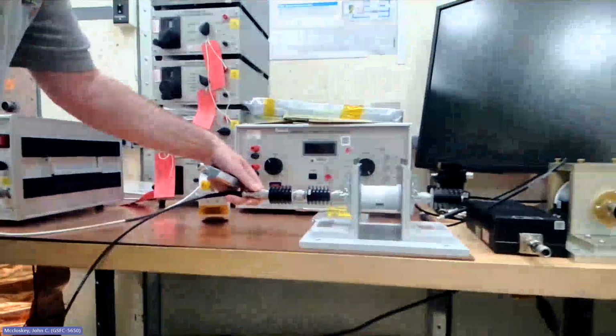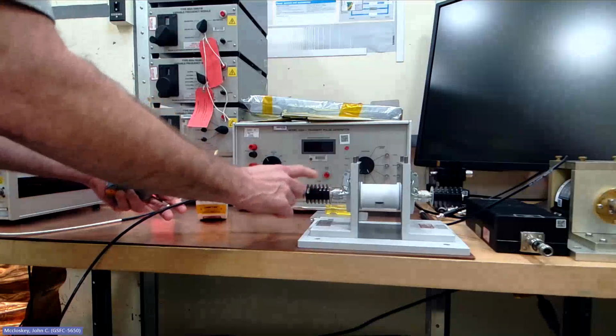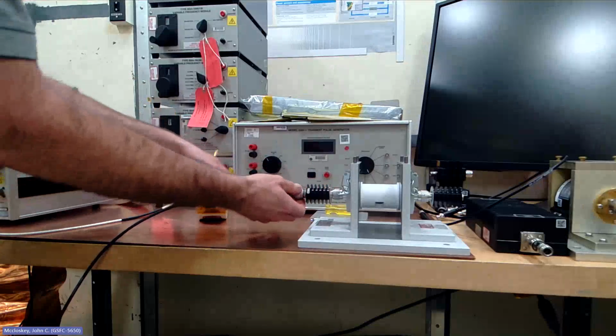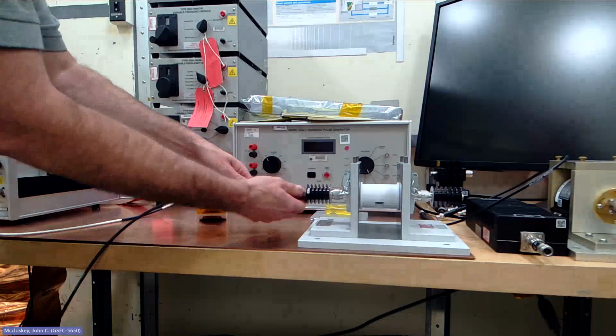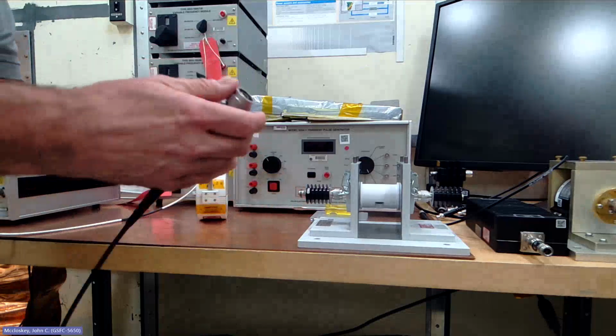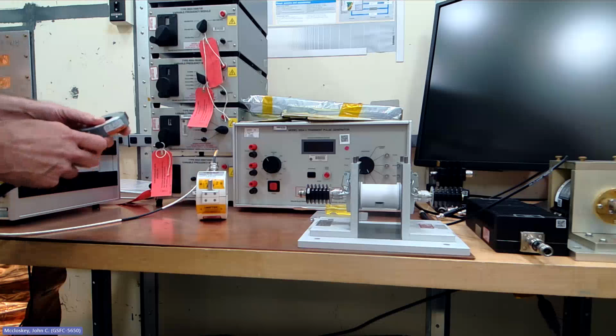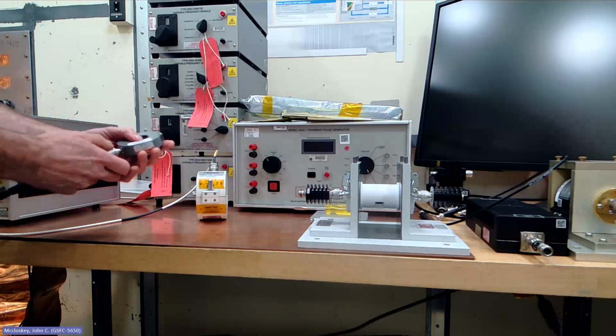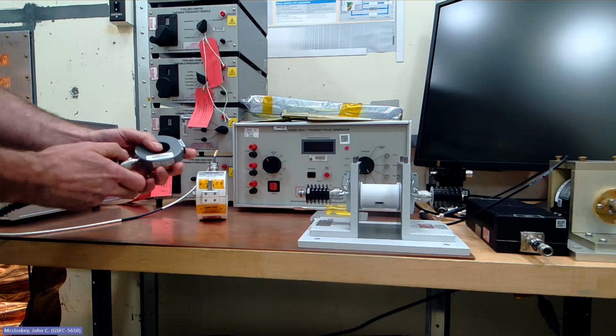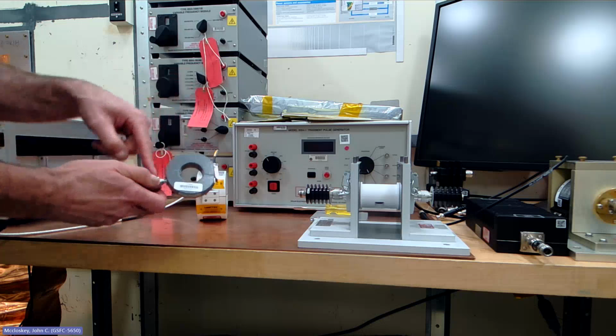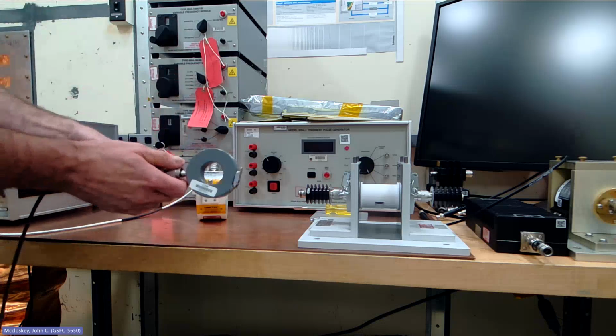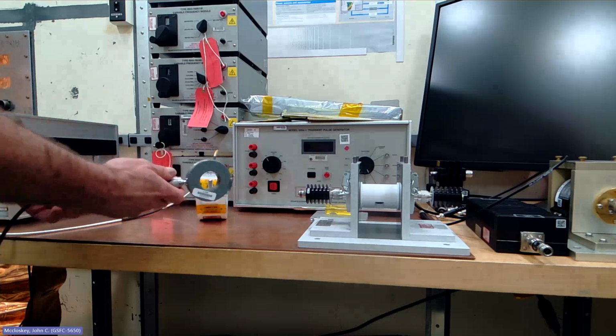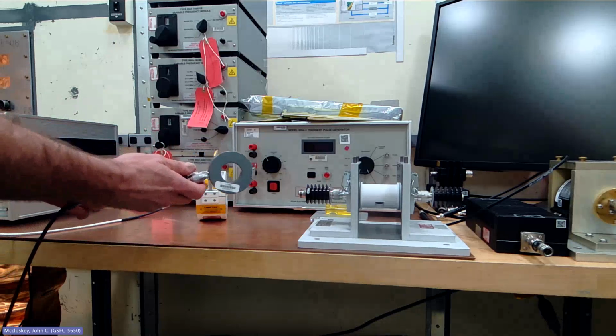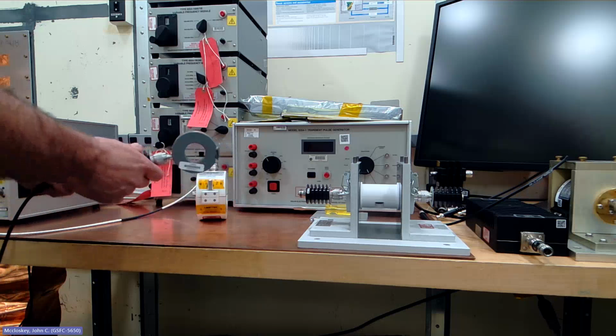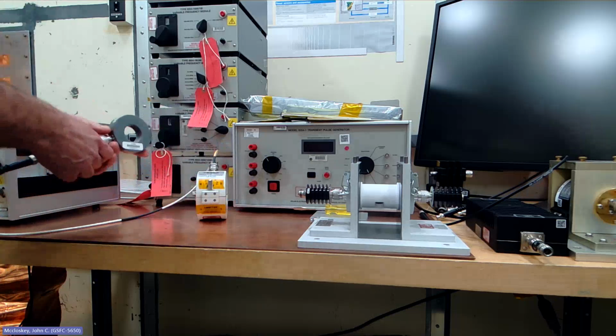I'm just taking one of these 20 dB attenuators. The 40 dB is made up of two 20 dB attenuators in series, so I'm just going to take one 20 dB attenuator. That's going to knock the signal down by a factor of 10. So if my expected range could be as high as 30 amps, giving me 30 volts at the output connector of the current probe, then the 20 dB attenuator could knock that down to a maximum level of about 3 volts at the output. So I'm going to be looking for a maximum level on the order of 3 volts on the scope.